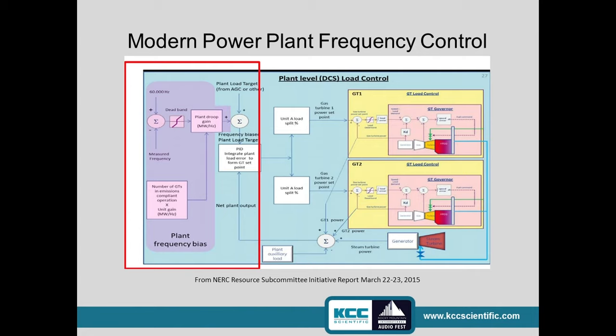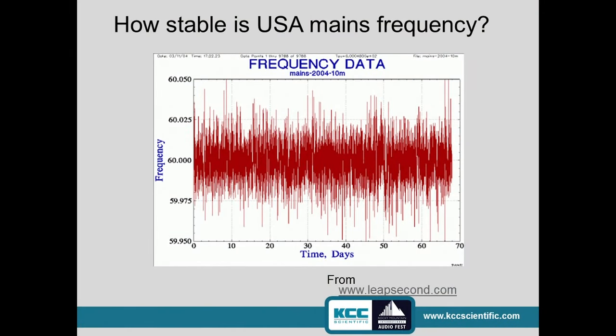There is a programmed dead band in the way frequency is controlled, which means it's going to go way down before anything happens to bring it back up, and vice versa — and that's on purpose. You can't jerk a 50-ton flywheel around back and forth; you've got to do it slowly and gently, which means you're going to get some movement of that frequency up and down. It's unavoidable. Automated systems today do a much better job than a master clock could have.